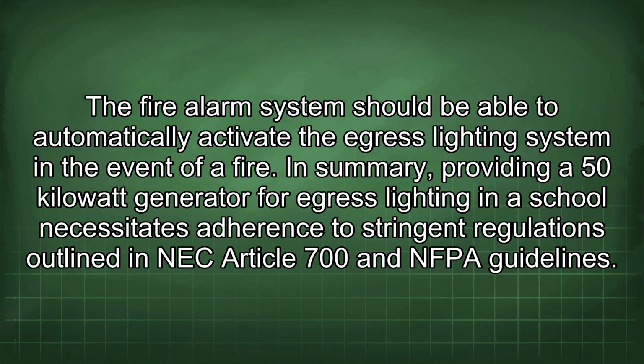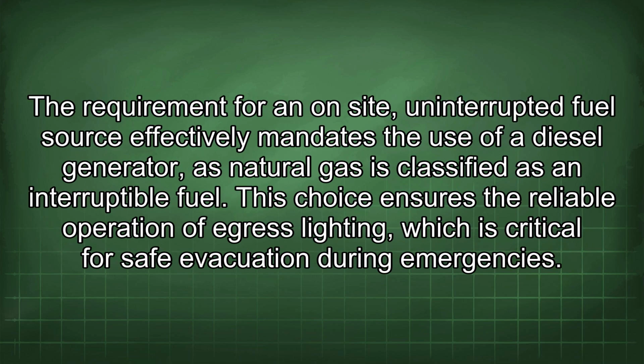In summary, providing a 50 kilowatt generator for egress lighting in a school necessitates adherence to stringent regulations outlined in NEC Article 700 and NFPA guidelines. The requirement for an on-site, uninterrupted fuel source effectively mandates the use of a diesel generator, as natural gas is classified as an interruptible fuel. This choice ensures the reliable operation of egress lighting, which is critical for safe evacuation during emergencies.